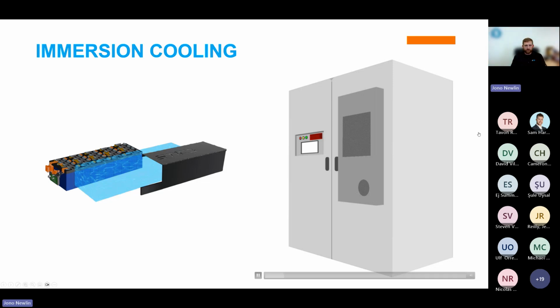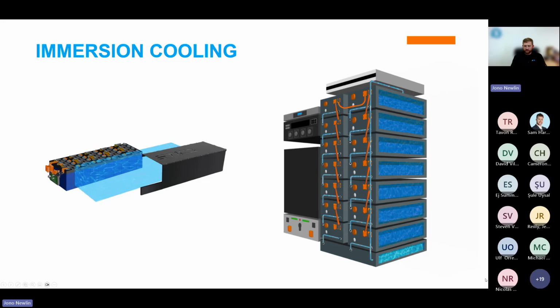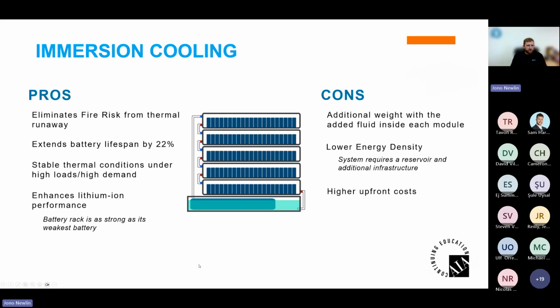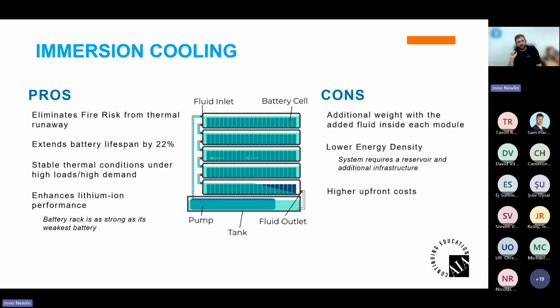As we look at immersion cooling, if I can advance the slide here, there we go. Immersion cooling, you have the pros. It eliminates the fire risk from thermal runaway. Now this is key, and this is very interesting because we're talking about cooling, right? We're looking at performance of batteries, but what do we remember back to those constraints for the critical risks for BESS? AHJs and communities are worried about deploying these.